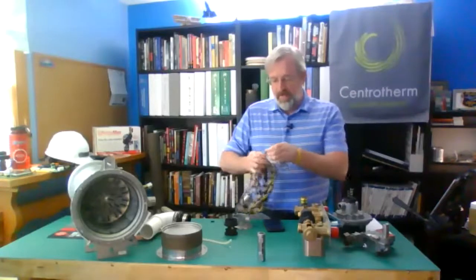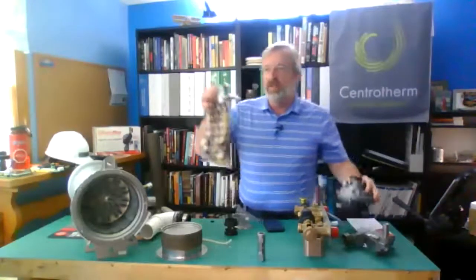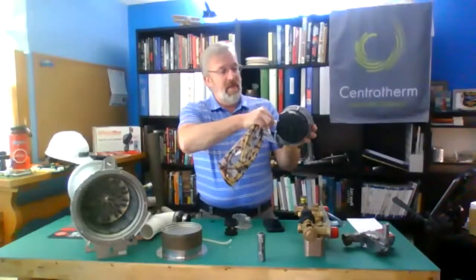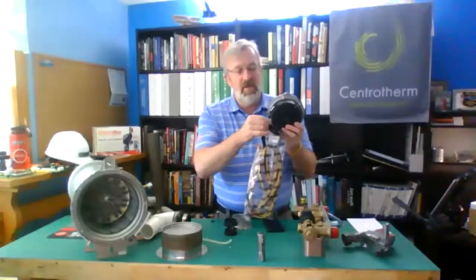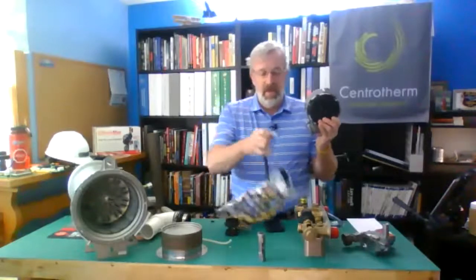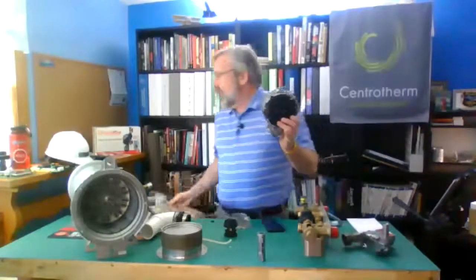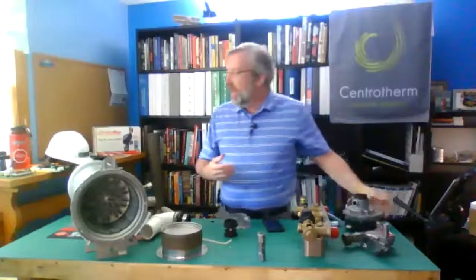So on these fans, there are 2 wires that connect to them. This is a 4-wire Molex plug, and that connects right there. That's my fan speed and modulation cable. It also, when my unit's powered, tells it to be off. So if I've got my power wire connected here, I've got my 120 volts, I have my unit switched on, and I disconnect this cable, I am no longer telling my fan not to run. So when I do that, the fan's going to run, and it's going to run to its full speed.